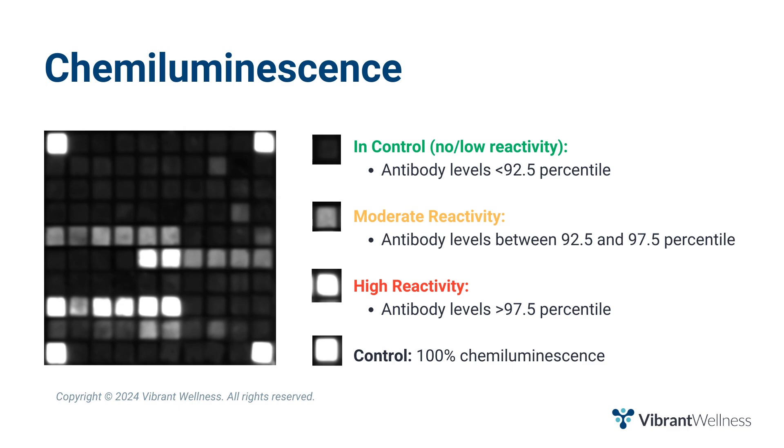The pillar plate is then submerged into the patient blood sample, allowing for simultaneous analysis of a large number of analytes from a single sample. Finally, a high-resolution imager is used to simultaneously detect chemiluminescent signals from labeled antigen-antibody reactions at each microchip throughout the multiplex microarray. Amplified chemiluminescent signals with high signal-to-noise ratio provide high sensitivity, meaning very few false negatives. This automated process allows for high-throughput, sensitive, and specific analysis of multiple biomarkers from minimal sample volumes.